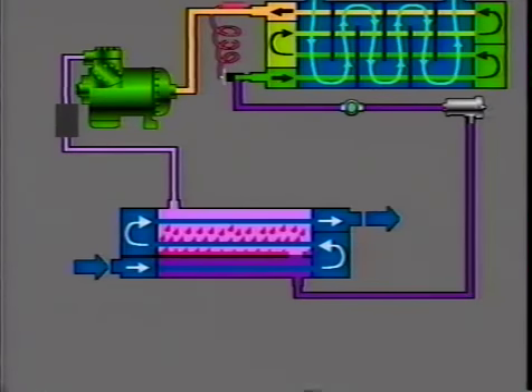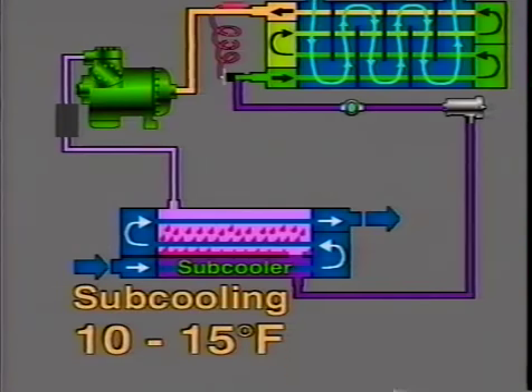In water-cooled condensers, refrigerant enters the shell and condenses on the surface of the cold tubes. The refrigerant collects at the bottom of the condenser, then flows through the subcooler. Refrigerant then enters the liquid line with 10 to 15 degrees Fahrenheit of subcooling.